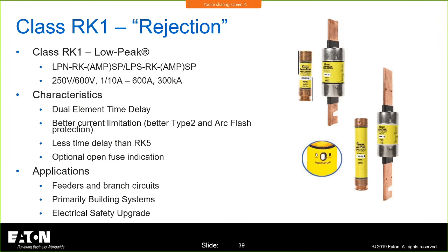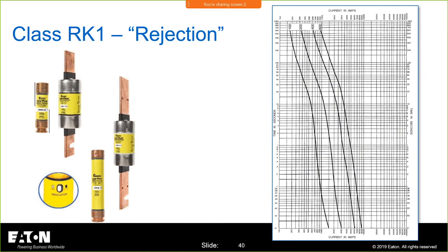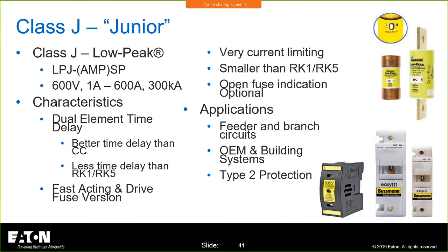But you'll see this on feeders and branch circuits, primary building electrical, and it's an electrical safety upgrade because, again, if you plotted these things side by side, you're going to cross a little bit further to the left at 0.01 seconds. So you're going to provide better, faster clearing times on lower currents. And that's a good thing.